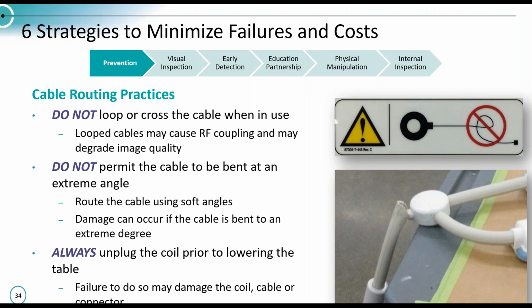It's always a good reminder for an end user to unplug the coil and move it out of the way prior to lowering the table. We get a lot of these coils coming in with crushed, pinched cables, and then we end up having to replace or rebuild the entire cable.